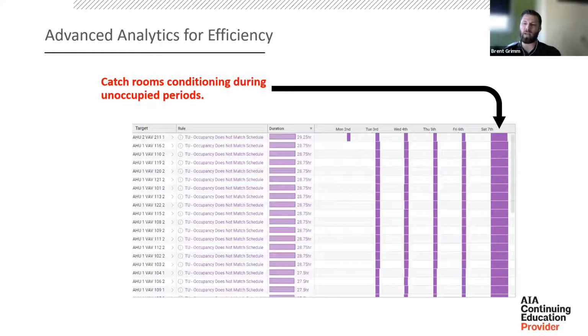Without analytics, it can actually be kind of difficult to determine which zones are not operating according to their schedule anymore. If the BAS does not have trending capabilities, then somebody has to be directly in front of the BAS when a room should be unoccupied and verify that the flow is being reduced to the point it needs to be and that the zone air set points are resetting appropriately. With analytics, all we have to do is load up custom schedules and assign those schedules to different rooms, and we just let the software do the heavy lifting. All we have to do at that point is log in, look at these alarms and see what's going on.